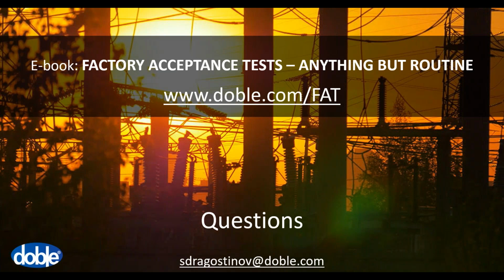Simon, there was one more question related to the PD, and this was the rejection level. So IEC 76 Part 3 defines the rejection level, and for a voltage level of 1.58 times rated voltage, the 1 hour level, the rejection level is 250 PC. For the following level of 1.2, the rejection level is 100 PC. Also very important is to observe the behavior of this PD level over the 1 hour period. It's a long period, and we can check the behavior of the PD.